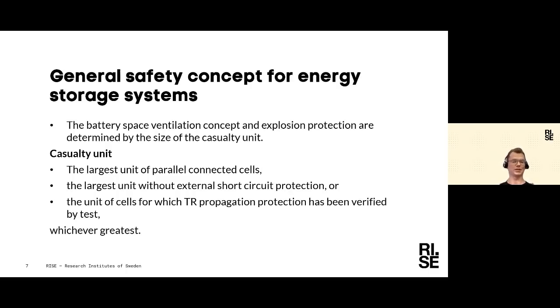In this room, our belief is that whatever ventilation or explosion protection is considered should be based on what you would define as the casualty unit. So we consider that to be the largest number of parallel connected cells, the largest unit without external short circuit protection, or the unit of cells for which you know that thermal runaway will not propagate further than that unit, whichever is greatest in these cases.